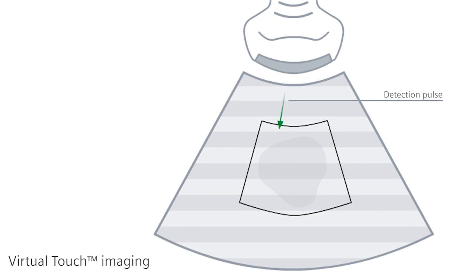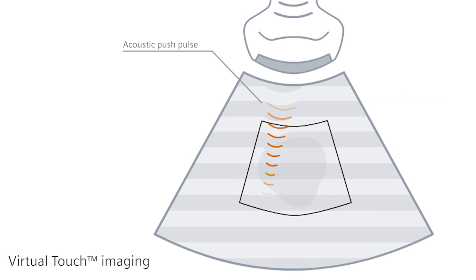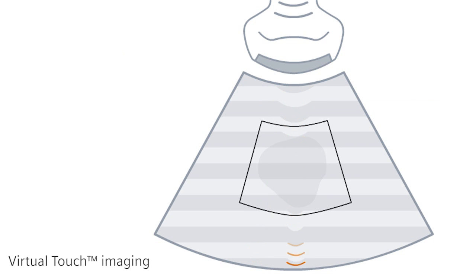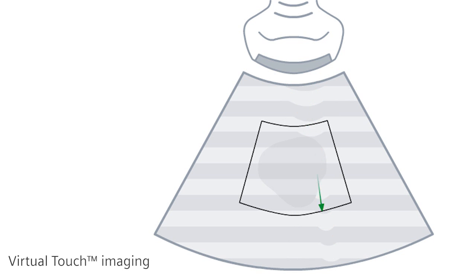The second form of elastography is virtual touch imaging, which electronically compresses the tissue by using a transducer with the help of a strong sound impulse. Due to the different stiffness of tissue, it will be displayed either in black and white or in color.